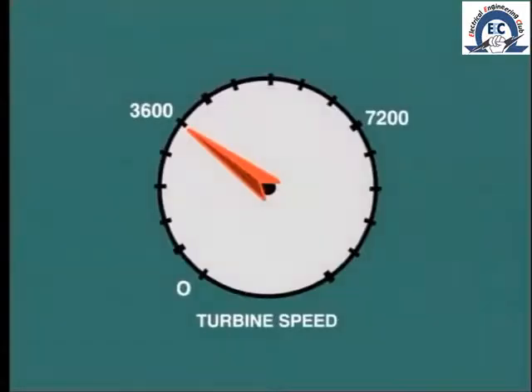In this case, steam flow to the turbine would continue, with the result that the speed would rapidly rise to 2 or 3 times normal. In practice, the speed would not get that far, because centrifugal force acting on the mechanical turbine and generator rotor would cause them to break up. Several instances have been reported of turbine blades and sectors of turbine wheels passing right through the turbine shell into the turbine room, with the potential for injury to plant staff and damage to other equipment.